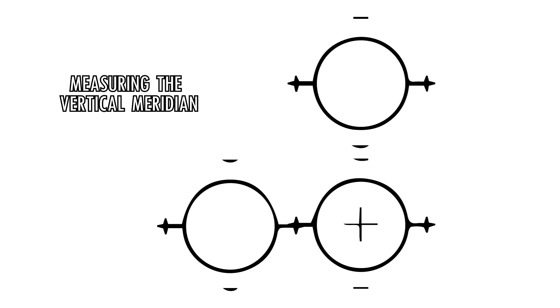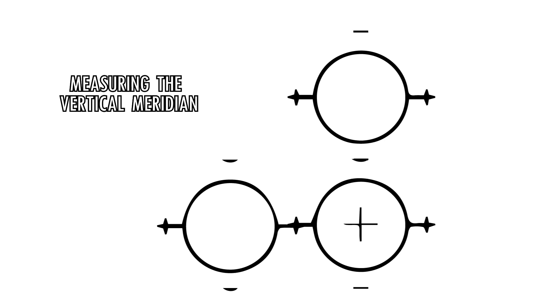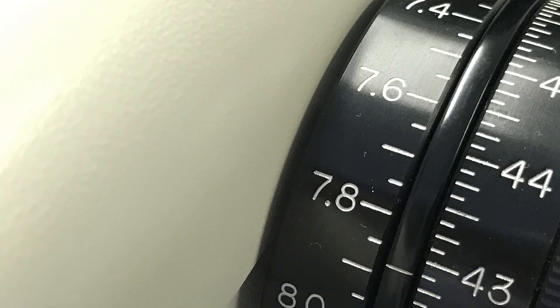When the horizontal meridian is found, the minus signs above or below the centre circle will be doubled. They must be made single by rotating the instrument's focusing knob. This brings the vertical meridian into proper focus. To measure the curvature in the vertical meridian, turn the right-hand vertical measuring drum until the short minus sign B and the longer minus sign B1 are superimposed. The scale on the right-hand drum then indicates the actual dioptric power of the corneal curvature in the vertical or near vertical meridian.